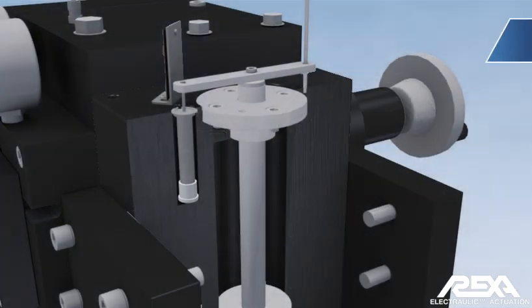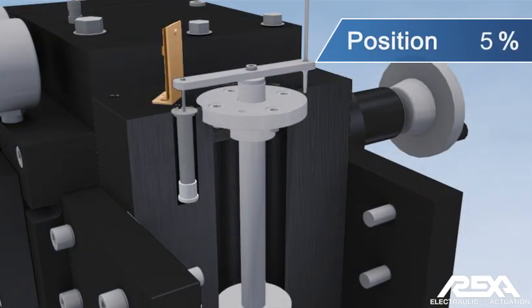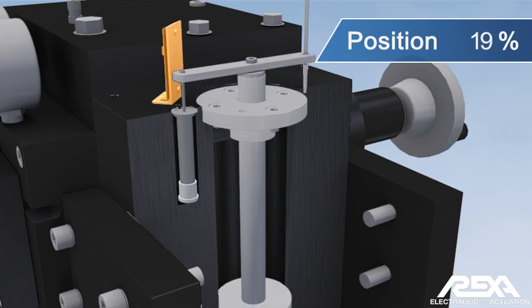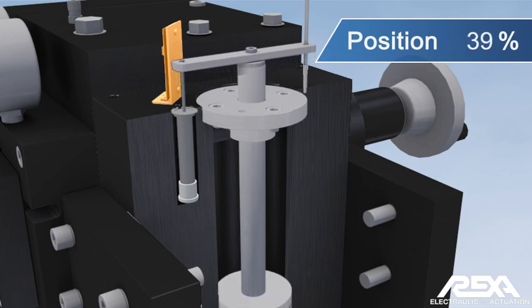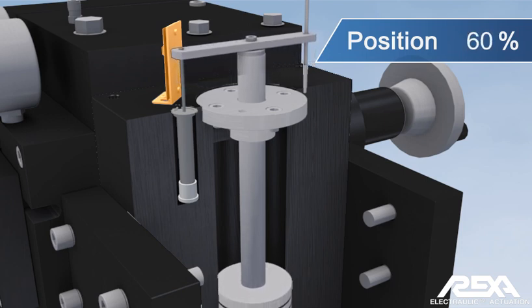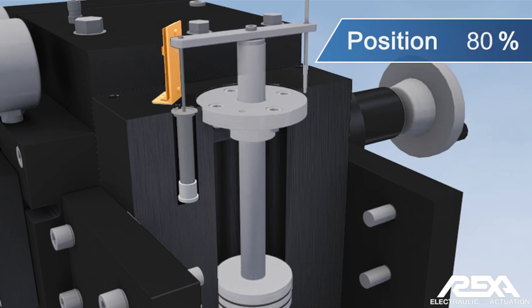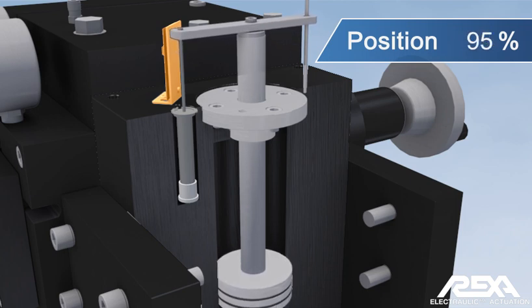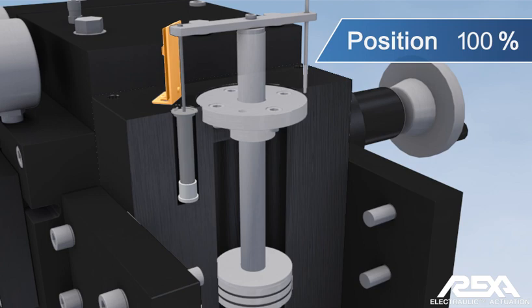Once the actuator has been calibrated, the information from the feedback board positions, set at position low and position high, is converted to an analog 4 to 20 milliamp signal by the PCB to represent 0 to 100% position indication and correspond to 4 to 20 milliamp signal low and signal high default settings.